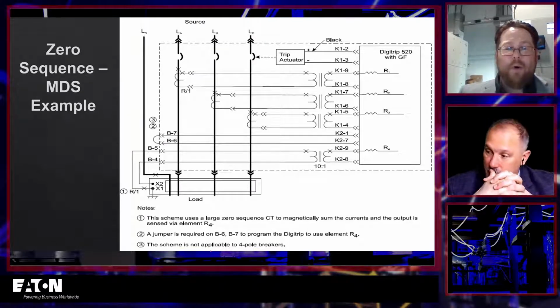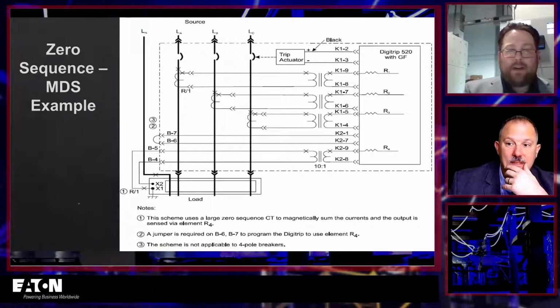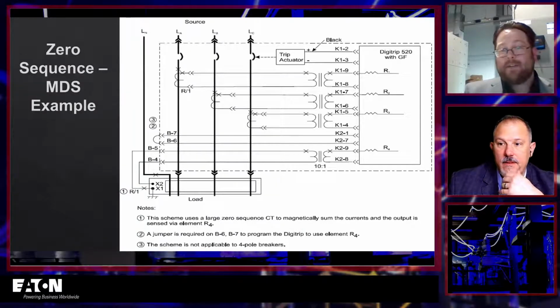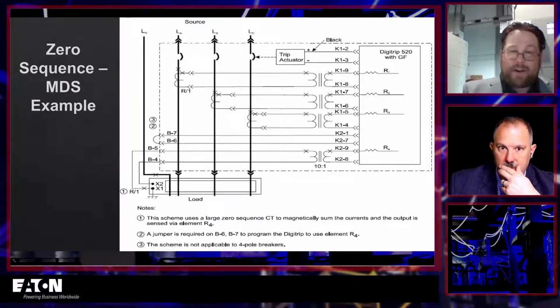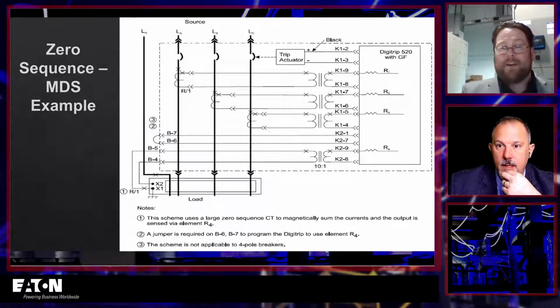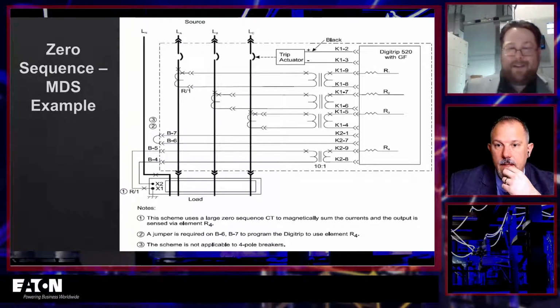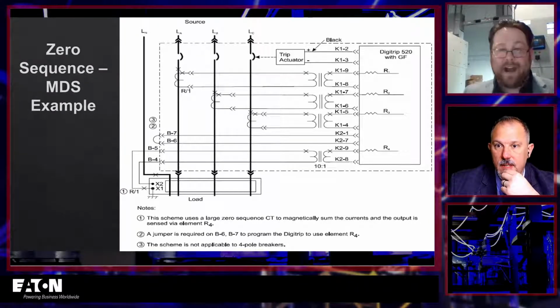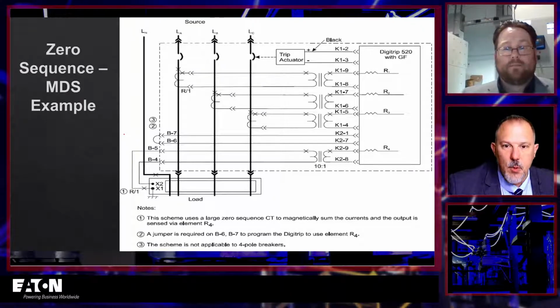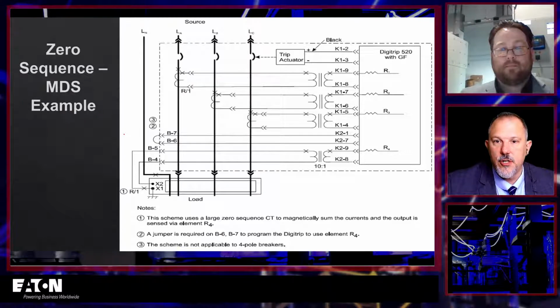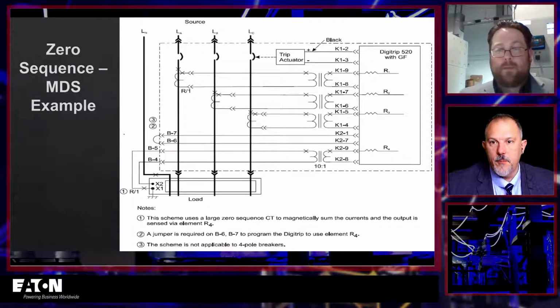So yeah, with the low voltage breakers, like you said, it's going to go back to the manufacturer. It's going to be specified when you choose the breaker based on its size, based on the short circuit rating or the interrupting rating of the devices in the switchgear, right? All that's going to feed into and say, you need this CT and here's the specs for that. That's right. Yep. So CT selection's important. Following the manufacturer's instructions, make sure it's paired up correctly with the trip units that you're using.